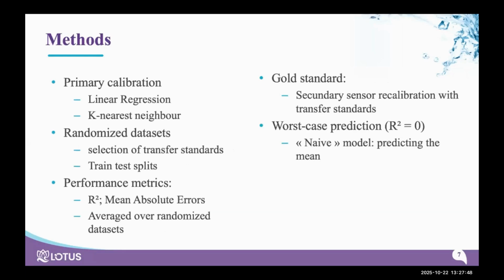We have very classical approaches. Our gold standard is that you want your calibration transfer to be better than recalibrating with transfer standard. Because if you recalibrate with the transfer standard you have, and you don't do better than that, it's pointless to do calibration transfer. You just recalibrate your sensor. So that's your gold standard, and your ideal is to be better than that, and you want to be better than the naive prediction, which is to predict the mean.